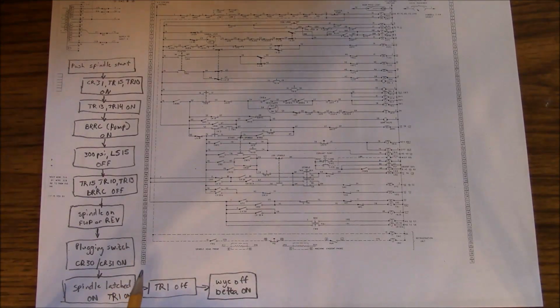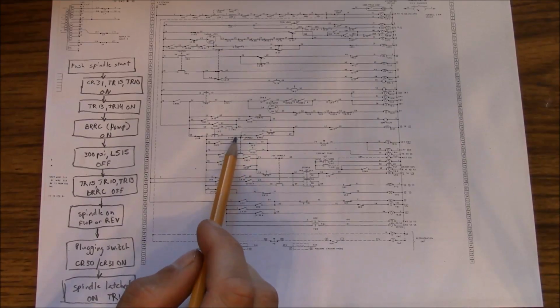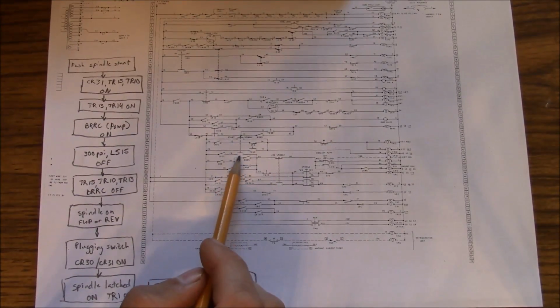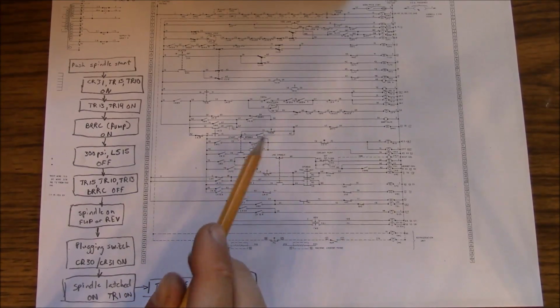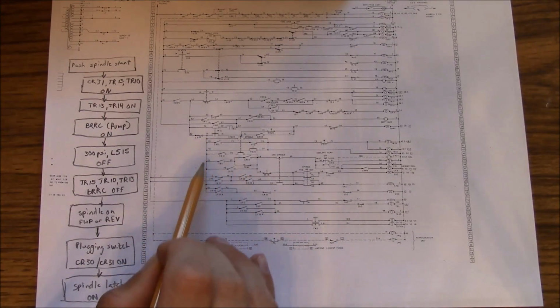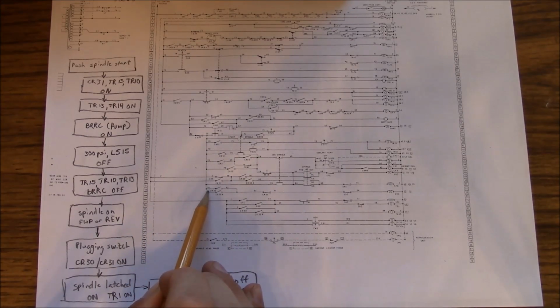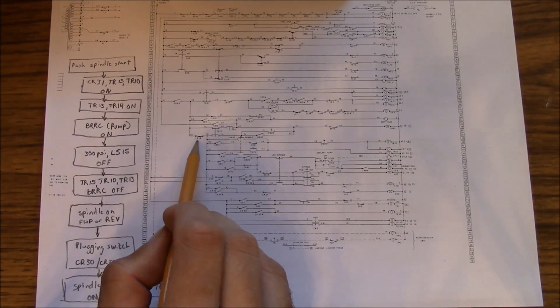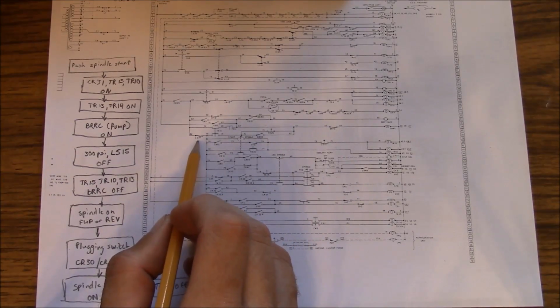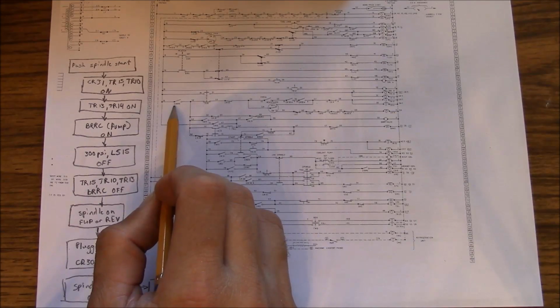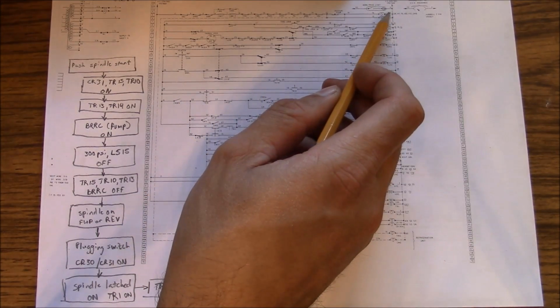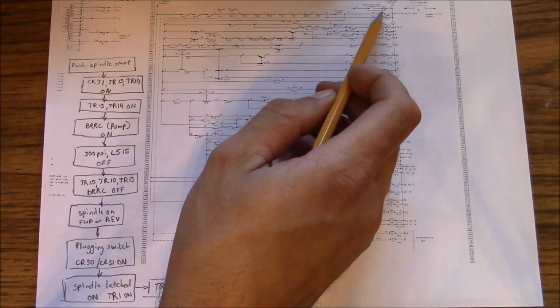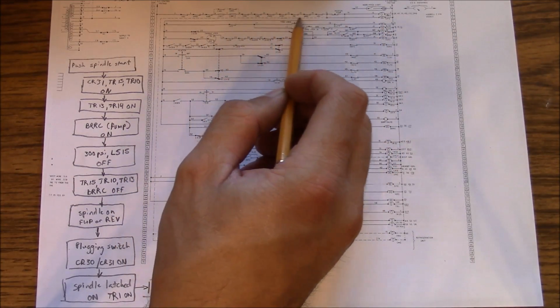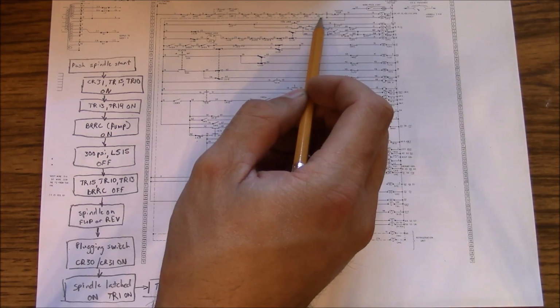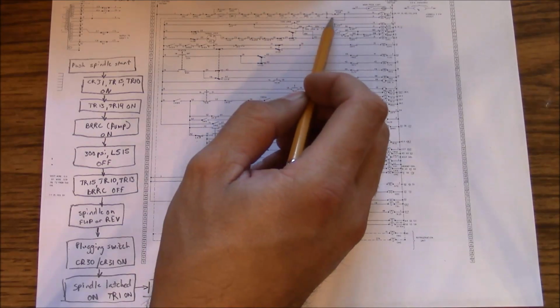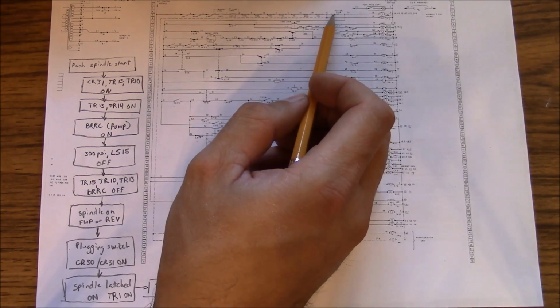The prerequisites for the spindle to start: here's the spindle start switch, a push button with 2 contacts, both normally open. You have to have power on this side of the switch for anything to work, which means limit switch 14 needs to be closed - that's just a safety switch, normally closed. Then CRMS has to be closed - that's the e-stop switch or e-stop relay. All these things in series are different conditions that cause the machine to go into e-stop, including the master stop or e-stop switch.